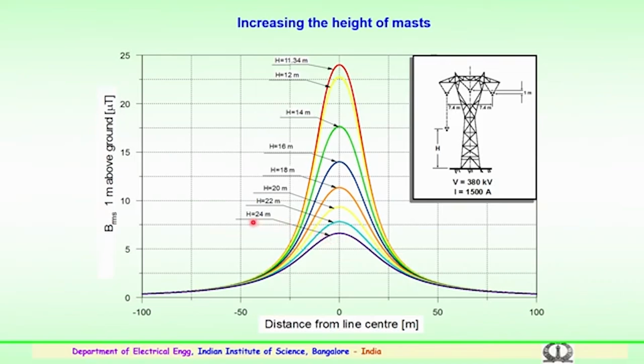You can see for various heights, that is 1 meter above the ground, the micro Tesla, that is the magnetic fields which could be generated because of the 1500 amp carrying capability of the conductors. So, the height H is considered from 11.34 meters to 12, 14 and up to 24 meters. You can very clearly see as the height decreases, the magnetic field increases. You can see the values typically for 11 meter clearance height with the conductor being charged at 1500 amps for a voltage level of 380 kV system, the magnetic field could be somewhere 23 to 24 micro Tesla.